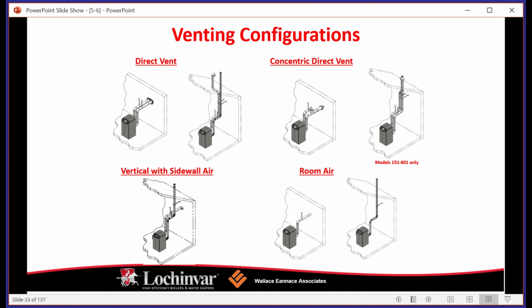Again, the boiler needs air for combustion. Obviously, air, fuel, and a source of ignition are what we need to make fire. If you have enough room in your boiler plant for the boiler to get its necessary cubic feet of air per minute, then you can pull room air. This is normally seen in bigger boiler plants, where you may have a louver that's interlocked to the boiler, so every time you get a call for heat, the louver opens and allows fresh air to flow into the room. Or you may just have a big enough room that you can pull your air.